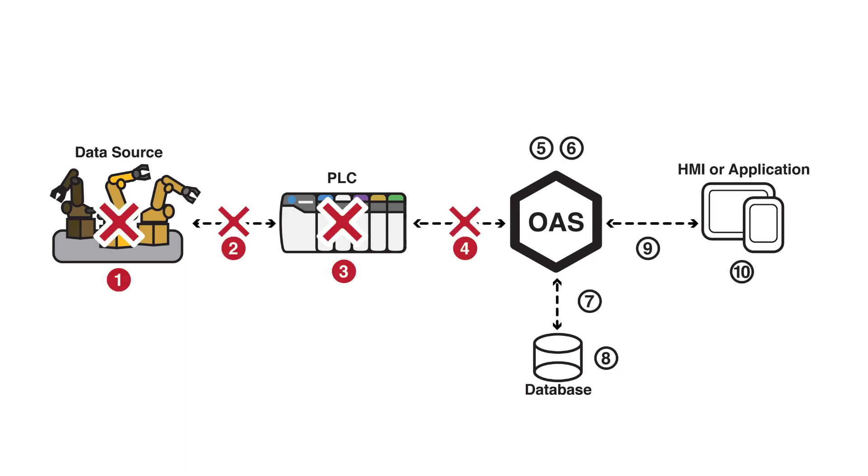One of the failure points is if any of the data source sensors go into failure, the communications between the controller and the data source is in failure, the controller itself maybe goes offline, or if the OAS engine is not able to communicate to the controller. Another point of failure is when the OAS engine itself is not available, or if the client application can't communicate to the OAS engine.